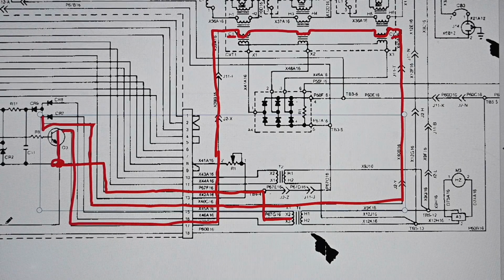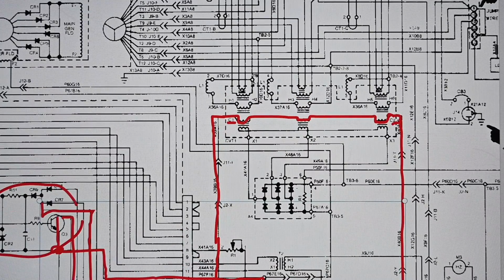So there's the complete path that the regulator is providing out to the magnetic amplifier. It's important to note how that path functions and the test points you might want to use if you suspect a problem in that part of the circuit. It's also really important to notice that this regulator, all of this circuitry, does not actually connect directly to the field windings up here. There's a big misconception that Q3 is somehow providing a direct connection into this field, but it's actually not - Q3 is only driving the control winding of the magnetic amplifier.